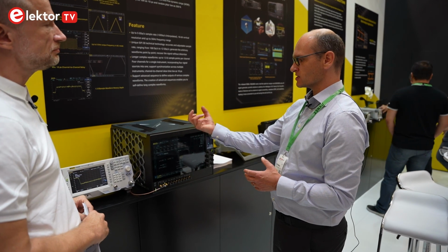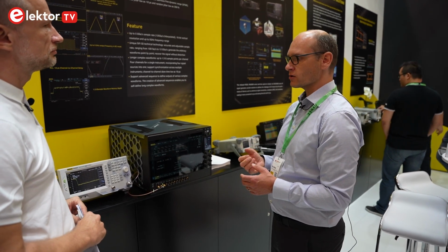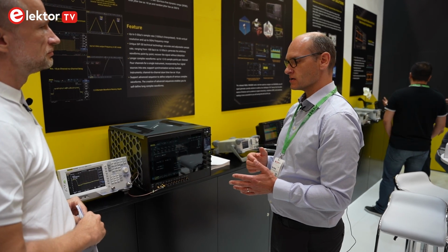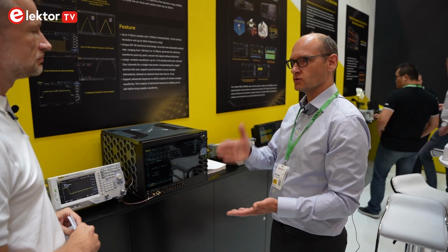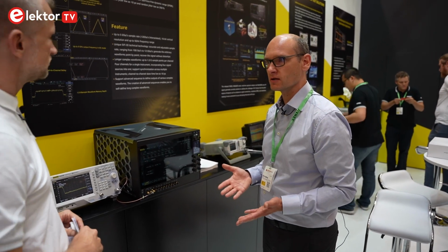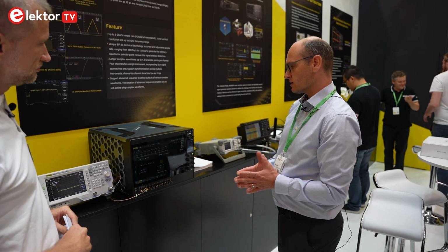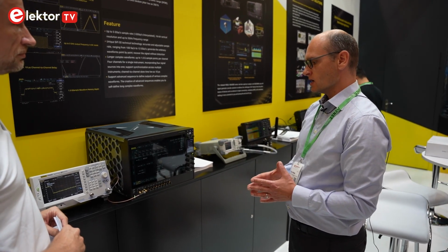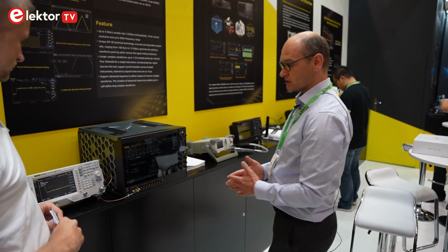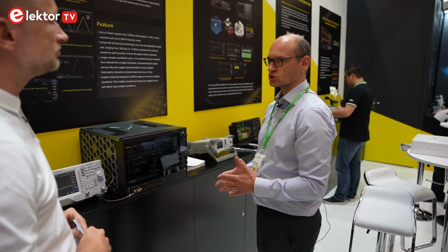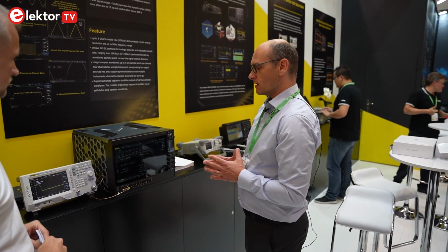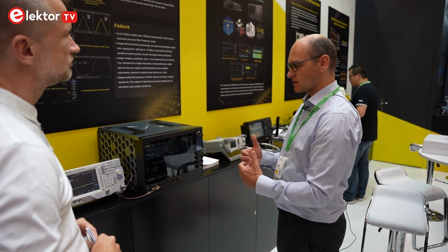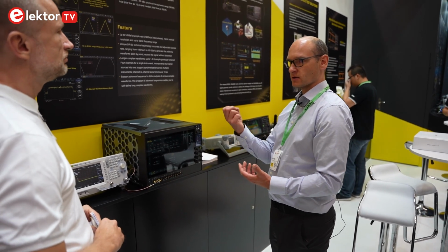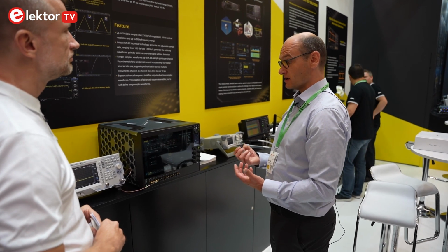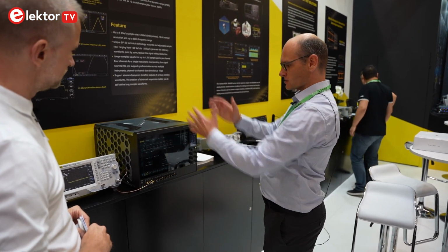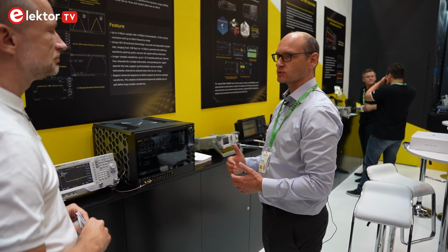Or you have also a digital jump insert on the rear side where you can bring in a pattern. With these algorithms according to your need, you can make jump signals like a Bluetooth signal, which is a jump signal. Such capabilities are possible with this test device. We also have the possibility to make a very, very good synchronization of each channel in the picosecond range. Because this test device is also designed for quantum computing, to stimulate the qubits. We also have the capability, if required, to extend the boxes, and we can combine different boxes up to 220 channels.